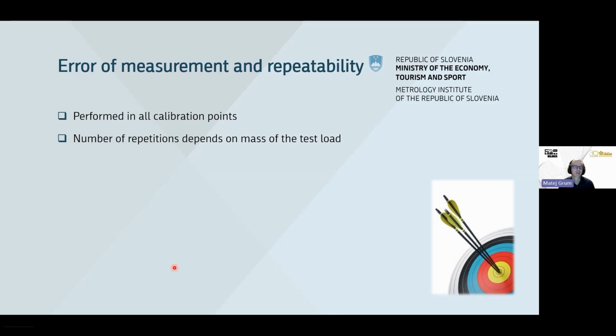Measurements which are necessary to evaluate the error of measurement and repeatability of the instrument are performed in all calibration points, and the number of repetitions depends on the mass of the test load. For larger masses, it is expected to carry out a smaller number of measurements. For smaller masses, the number of measurements could be higher. Based on these measurements, the mean indication is defined, and the standard deviation, which is then used to calculate the repeatability of measurement.